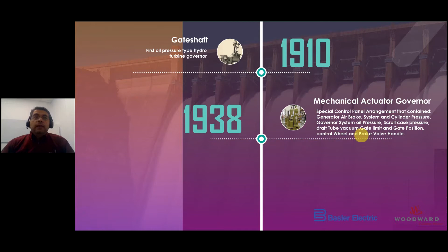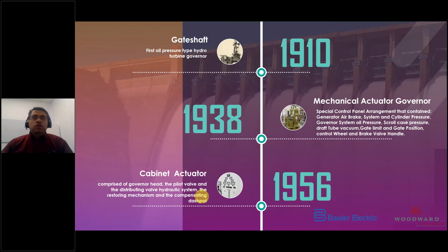By 1956, we improved our design. We came up with a cabinet actuator, so you can increase or decrease the speed, and control the frequency a bit. We also introduced the concept of the dashpot, which adds extra droop or compensating droop for controlling the turbine during startup and shutdown. This was a big step at that time.